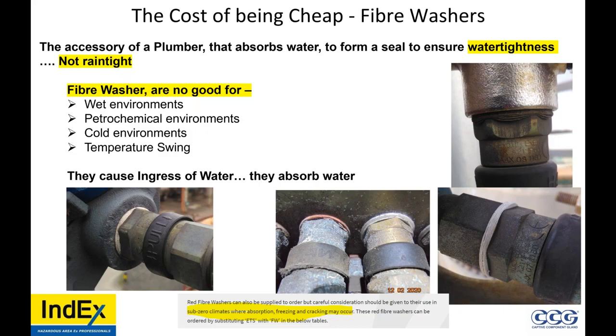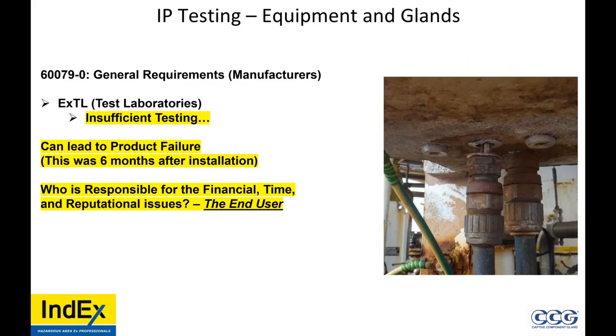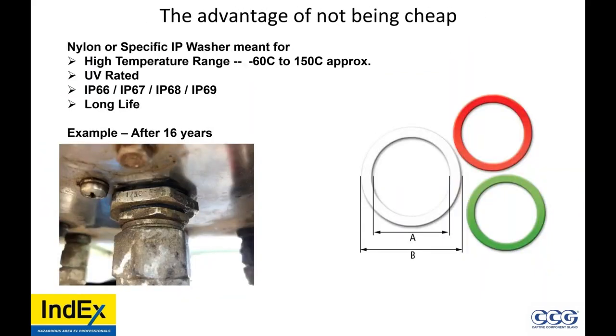So the only way to have a safe quality installation is to install the nylon, plastic, or rubber IP washer. Fiber washers, only indoors. No chemical processes, no petrochemical environments, no big temperature swings. They only absorb water and cause failure. Advantage of not being cheap. Maybe it costs you an extra 1 cent per nylon or specific IP washer.